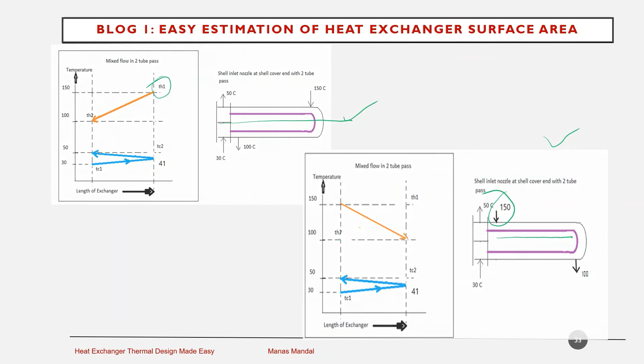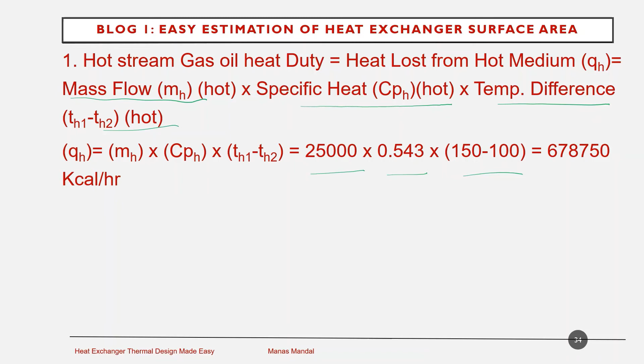Hot stream gas oil heat duty can be calculated from gas oil mass flow, specific heat of gas oil, and temperature difference of gas oil. So hot fluid heat duty is mH multiplied by Cph multiplied by Th1 minus Th2, which is nothing but 25,000 multiplied by 0.543 multiplied by 150 minus 100, which will give us 678,750 kilocalorie per hour heat duty.